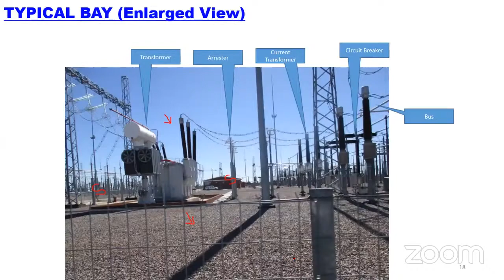If you look at the transformer, there is a foundation here, designed by the civil engineers based on the size of the transformer. Since the transformer contains oil and winding, if there is an abnormal condition causing oil spillover, this foundation helps collect the oil without it spilling across the substation. That should not happen, and this is international practice, even though some local substations may not have it. This is called the transformer sump, built along the periphery of the substation. It has concrete work about 600 mm deep, roughly 2 feet, which helps collect the transformer oil during an abnormal condition.